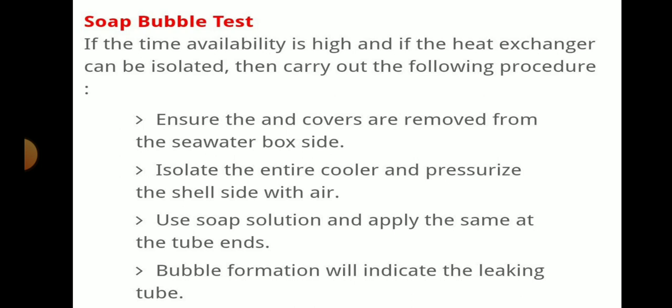Soap bubble test: if the time availability is high and the heat exchanger can be isolated, then we can use the soap bubble test. Ensure the end covers are removed from the seawater box.